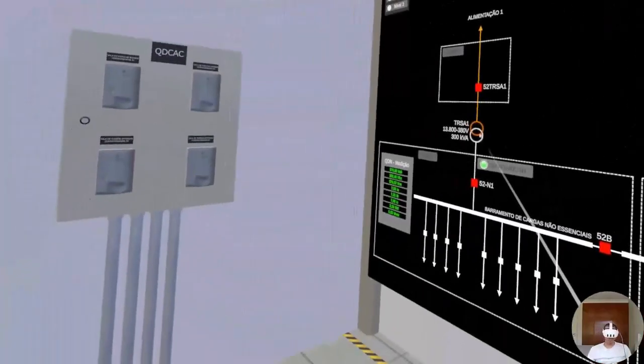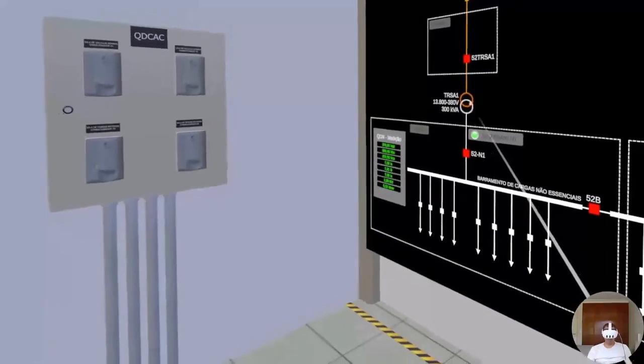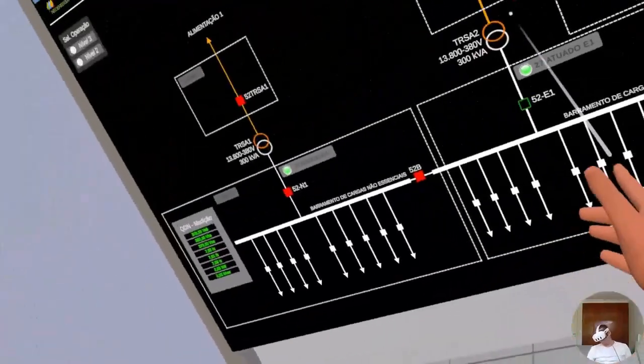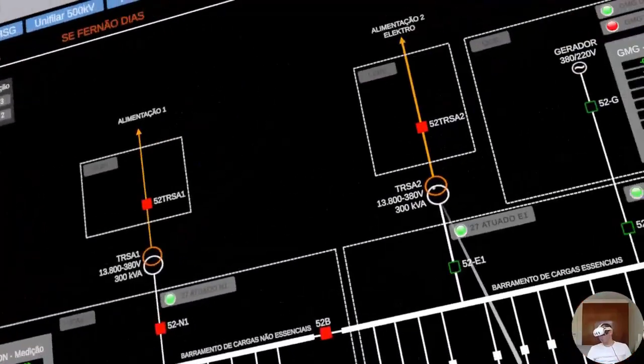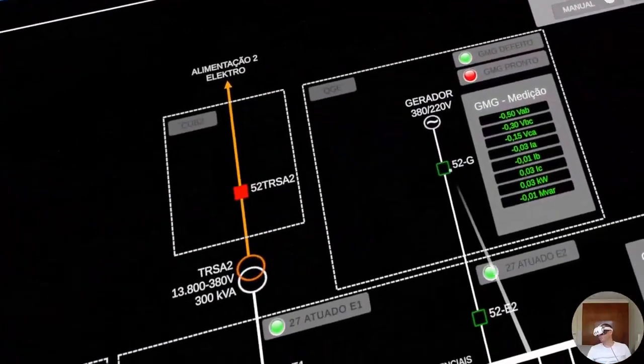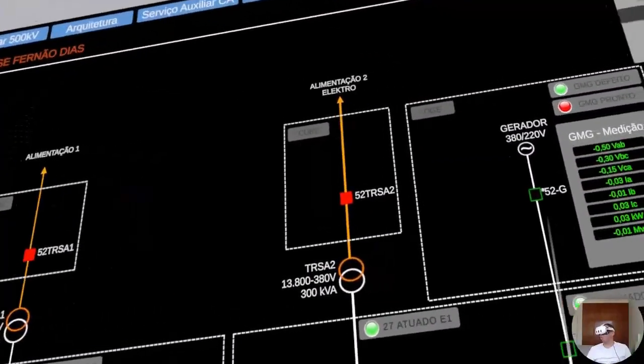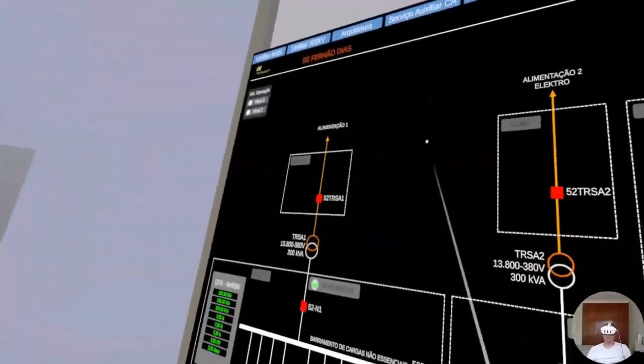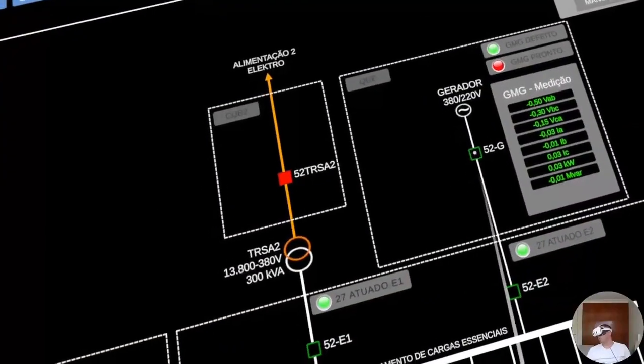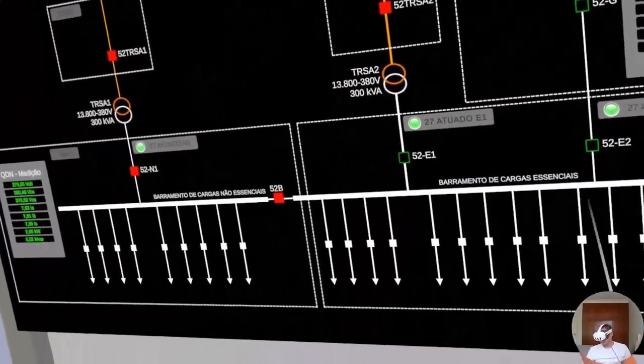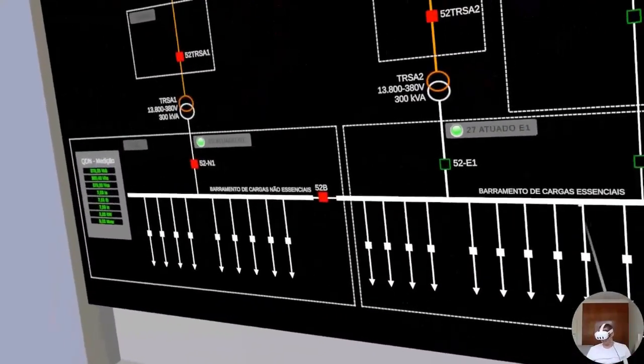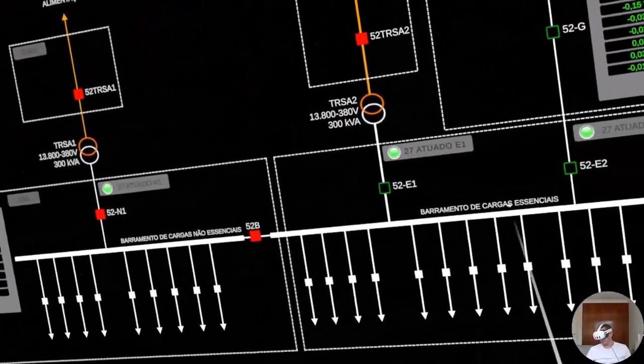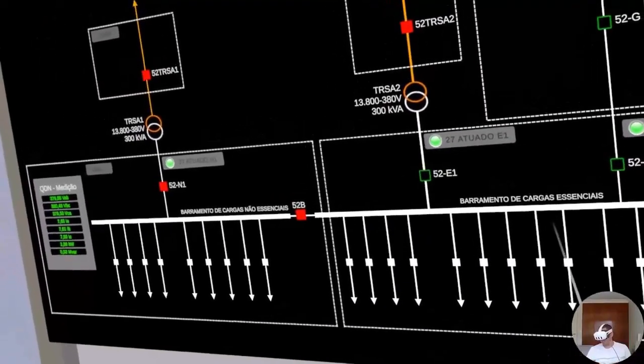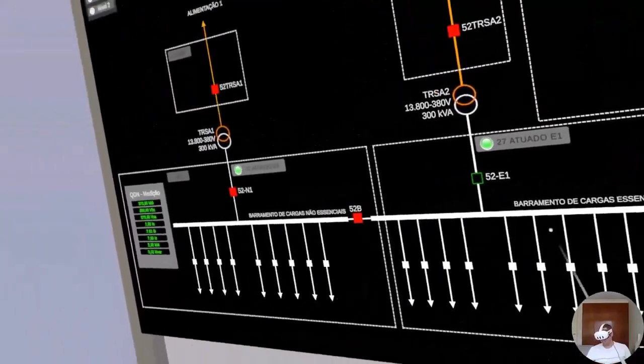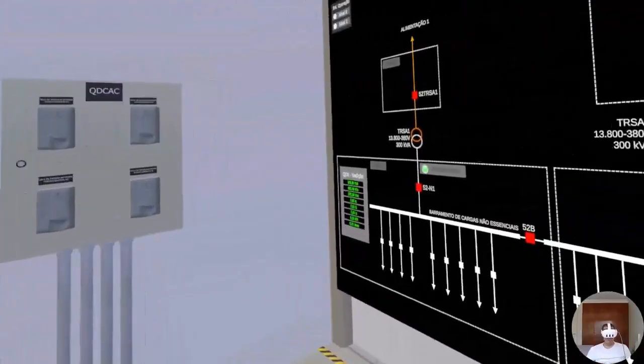So we have here this transformer right here, auxiliary service, and we have this other auxiliary service transformer. And here we have an emergency diesel group that in the absence of both power sources, the diesel starts up and it's able to power the bus bars. The ideal way is to operate the essential loads first. As soon as it's back to normal, we bring in the non-essential loads.